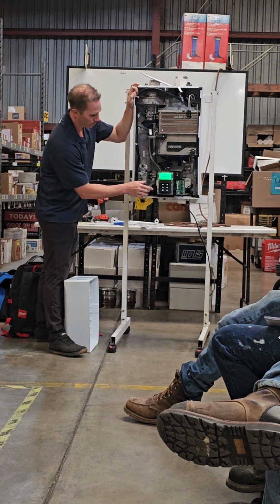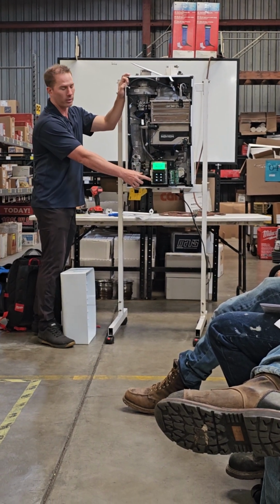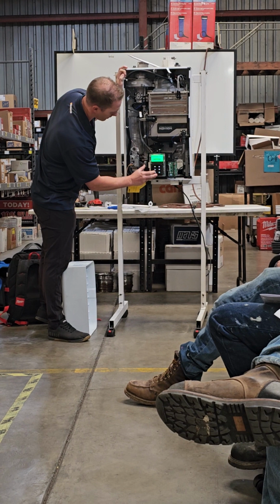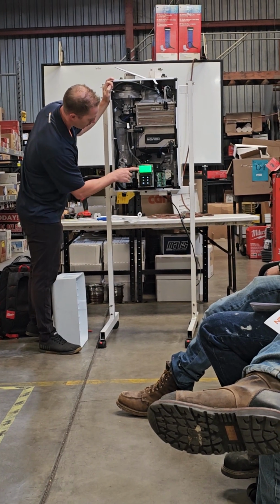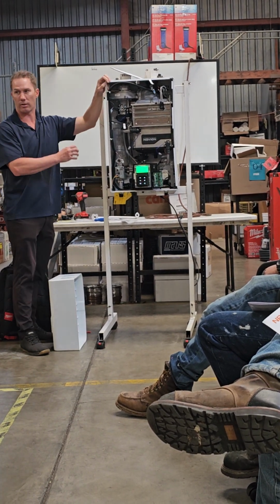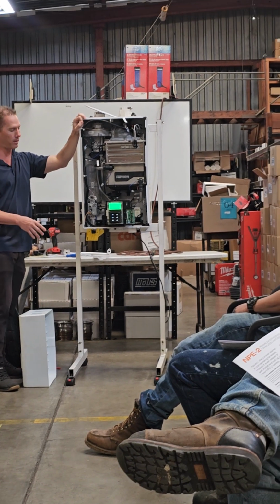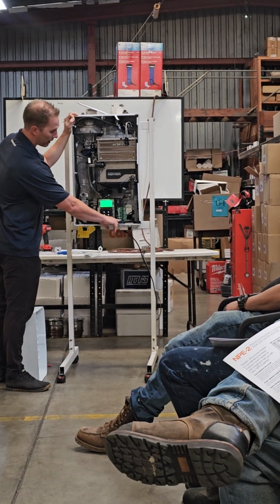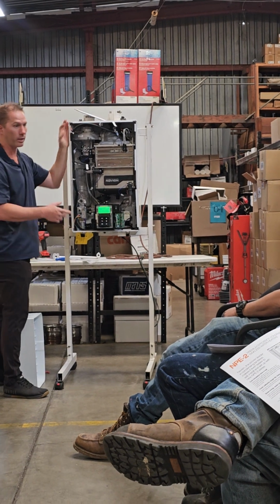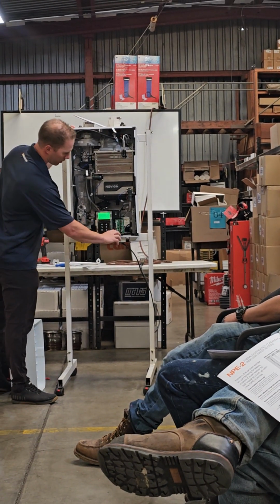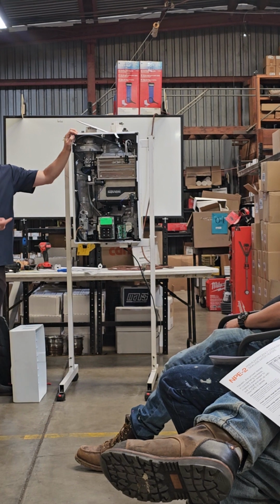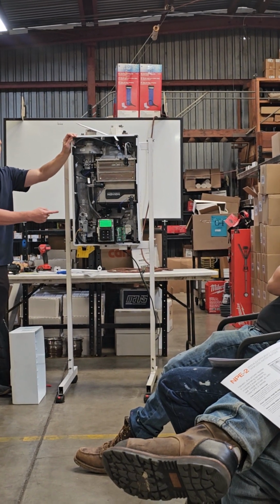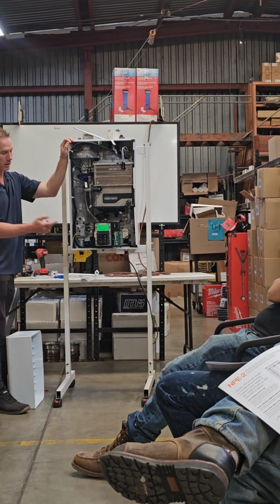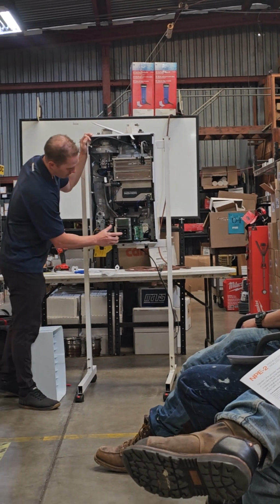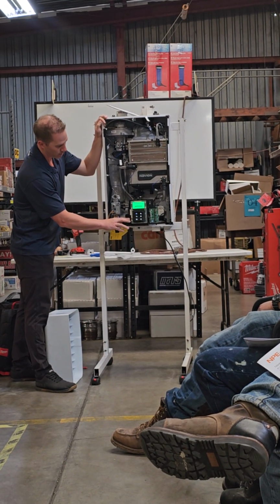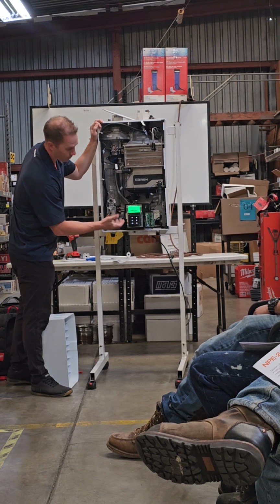Next is natural gas or propane, so I'm not going to flip dip switch number 1 yet—I'll just select propane in the wizard. The first thing that happens is a warning that the unit isn't configured properly for the settings. That's because a lot of guys read in the manual to flip dip switch 1, do that, then call me saying it's still warning them it's not configured—it's because they didn't flip the dip switch correctly. So I'll hit back, flip dip switch 1 here, select propane, and we're good to go.